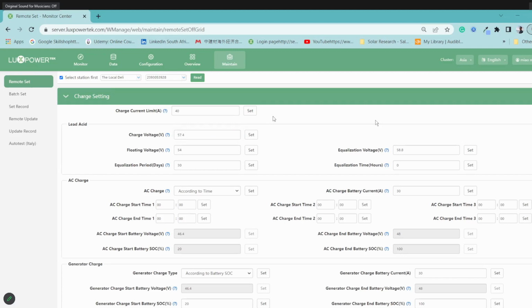When you get to this point and you change it, you'll notice that when the client monitors the system, it still shows the SoC, but it only goes up to between 90 to 98%. That information is not accurate because of what you're doing here. If in some situations it actually does read 98% accurately, that's a problem on the BMS side, because with the shorter batteries, 54 volts, so 55, 55.5 volts should bring it up to 100%. From our side, we're busy working on new firmware that will assist with this.